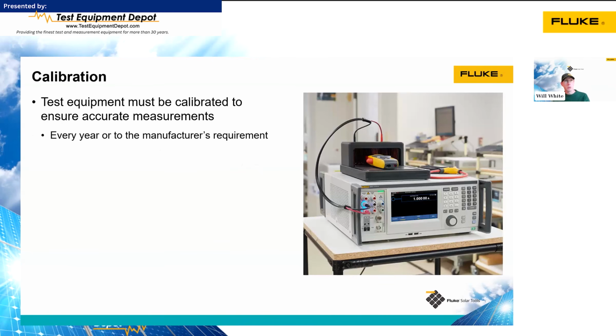And of course, our test tools need to be calibrated. Most Fluke tools require annual calibration, or read whatever the manufacturer's specifications say. Some operations and maintenance contracts will require calibration before you go out to the job, and they're going to want to see an actual certificate of calibration. Fluke has calibration services, so we can provide those as well.